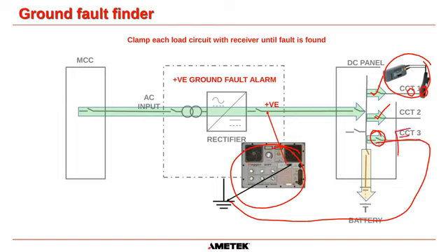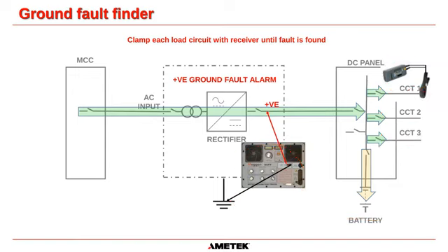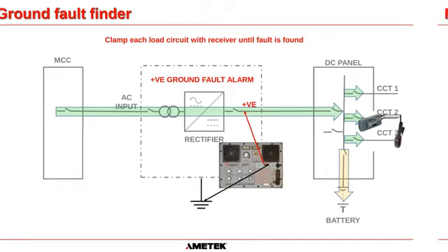And then if you have a sub panel fed here, you can take that amp clamp receiver and go on each of the sub loads and find out which individual one still has the signal. And that will tell you where the ground fault is. This is an excellent piece of equipment. It's quite expensive, but if you do get frequent DC ground faults at your system, it is very easy to set up and find those ground faults without having to disconnect any of your loads and without jeopardizing any of your loads. Okay. And these pictures are just showing you moving the amp clamp to the different positions.